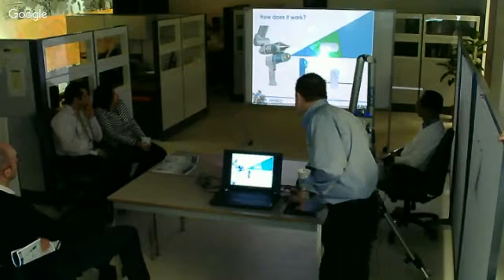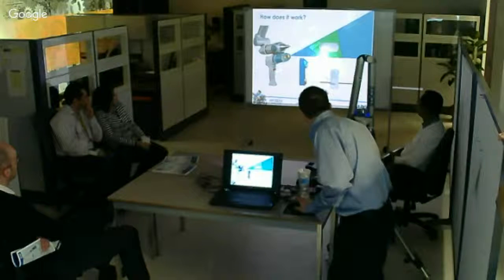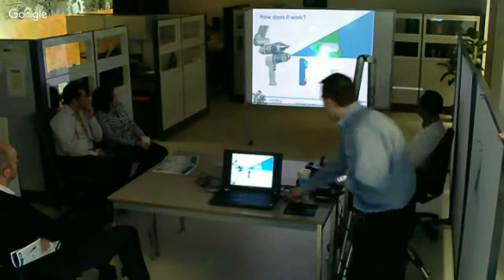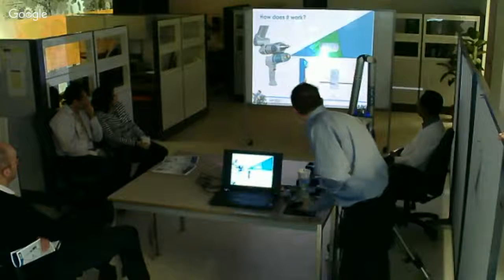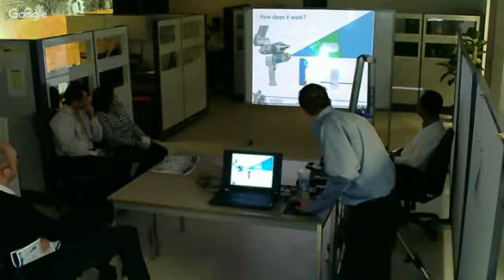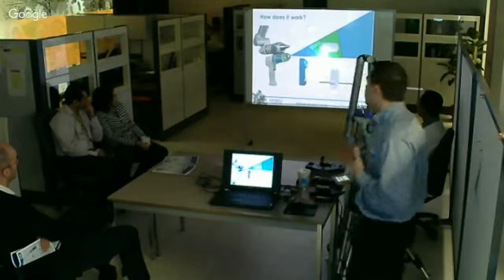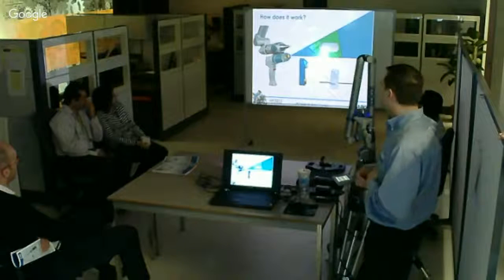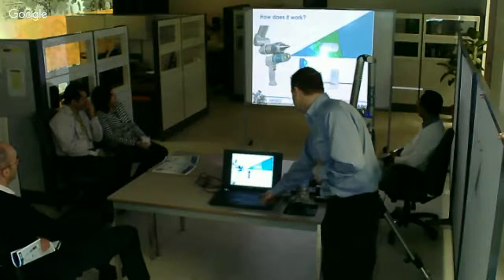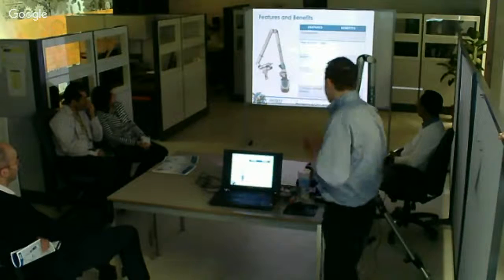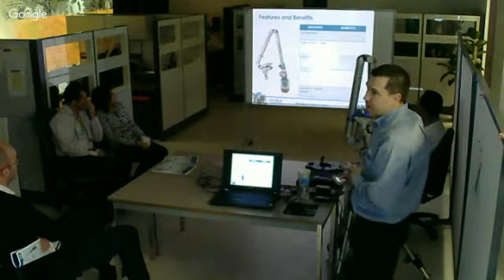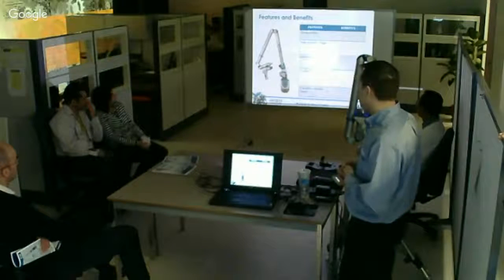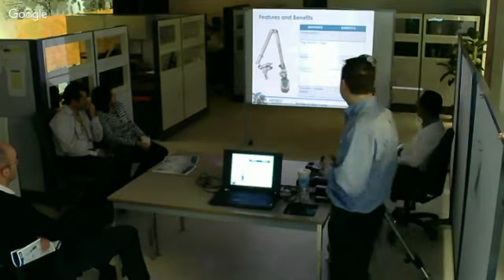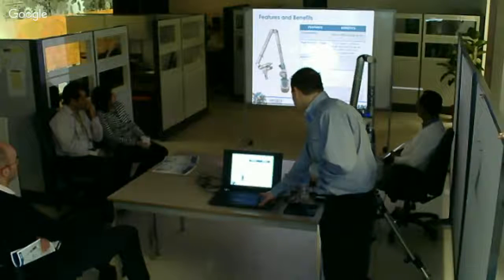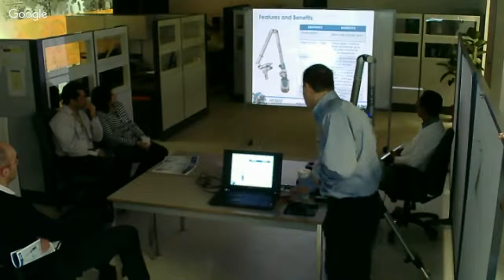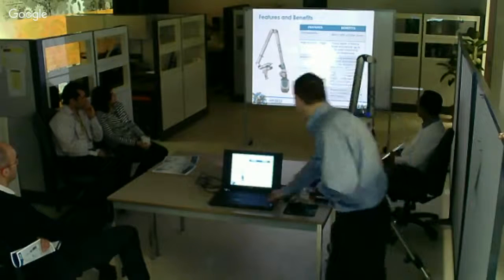So the laser itself, like I said earlier, is a line, so you can see it come out, and it reflects back into the camera. It comes out of the laser, back into the camera, and it does the trigonometry to figure out where it is in space and creates that three-dimensional image. So, like I said, the automatic scan mode is changing for whether it's a black or a shiny part, and it's able to do that automatically. Works with all our edge arms, very compact and ergonomic design.